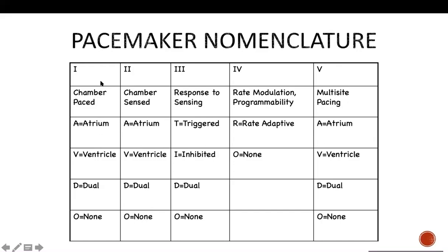So since it's a pacemaker, the first letter of the programming is what chamber it is going to pace. The second letter is what chamber it is going to sense. The third letter is what it is going to do in response to sensing. And the fourth one is rate response. So we'll start with the first letter. If we have a single chamber device in the ventricle, for example, in someone who has atrial fibrillation with slow ventricular response, you need a ventricular lead only to increase the ventricular rate. That is the need for the pacemaker, to avoid bradycardia.